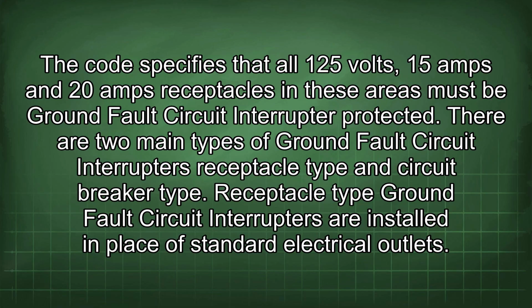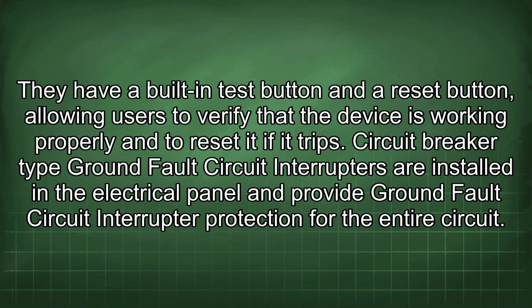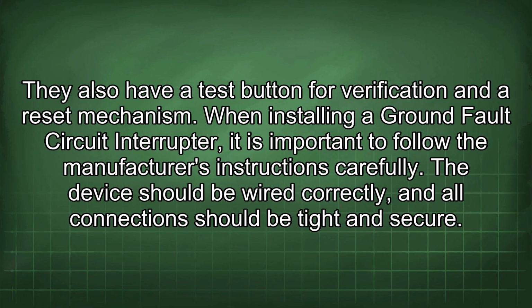Receptacle type ground fault circuit interrupters are installed in place of standard electrical outlets. They have a built-in test button and a reset button, allowing users to verify that the device is working properly and to reset it if it trips. Circuit breaker type ground fault circuit interrupters are installed in the electrical panel and provide ground fault circuit interrupter protection for the entire circuit. They also have a test button for verification and a reset mechanism.